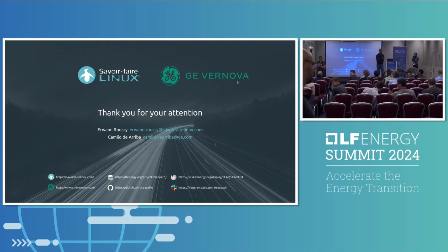Did you consider building a line differential protection with this, regarding the potential jitter and transmission delays in the transmission of the measurements? Yes. The aim of this platform is to cover transmission, distribution, generation, and to do that, we have distance, line differential. I mean, all the protection functions that you have in the conventional devices, we are porting everything into SEAPATH. Yes, of course.